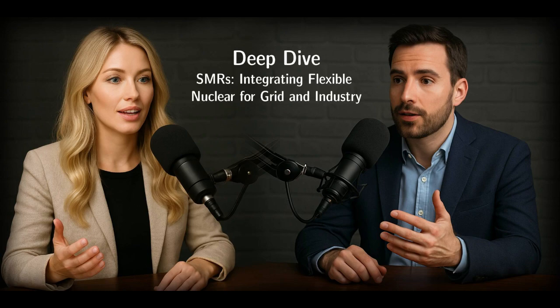Okay, let's touch on some critical engineering considerations as we wrap up. Integrating small modular reactors clearly needs advanced protection and controls. What are the key technical standards? Compliance is key. IEEE Standard 1547 is crucial, covering the interconnection requirements for distributed energy resources. It mandates things like voltage and frequency ride-through capability, participation in frequency response, strict limits on power quality issues like harmonic distortion and flicker, and anti-islanding protection. These are non-negotiable for safe grid connection.